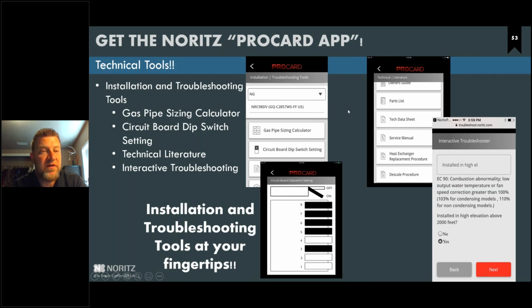So, as I said before, we do have an app called the ProCard app. With that, it does have gas pipe sizing. It does have this little circuit dip switch settings here. So if you are installing one of our units, you can just put in there the install of what you're doing, and then it'll bring up which dip switches you need to press. On that app too, if you're working on older units, it'll give you the owner's guide, parts list, tech data sheets, the service manual, how to replace a heat exchanger, how to descale that unit. It works with all the new units too, but it will give you literature on any one of our units all the way back to 2000.